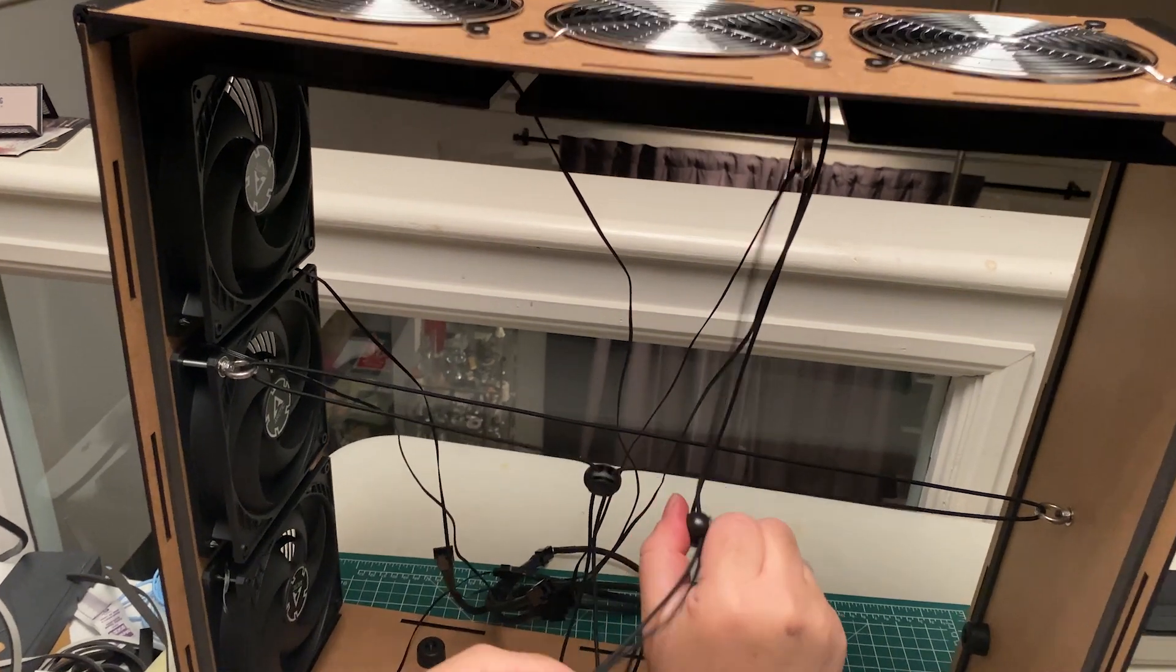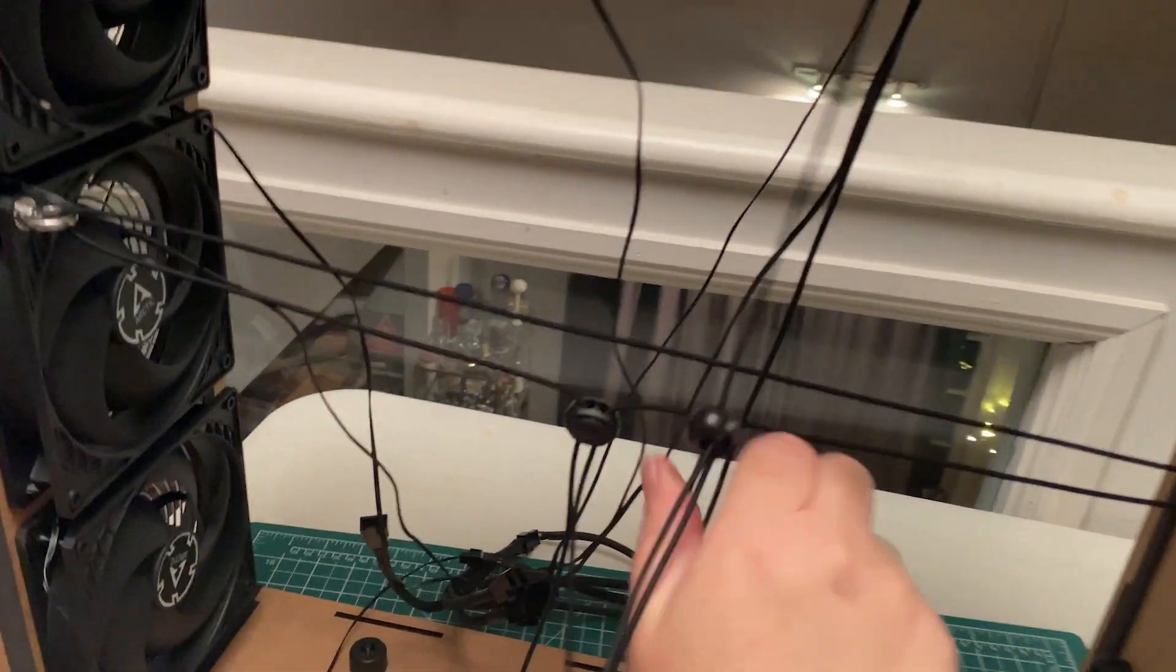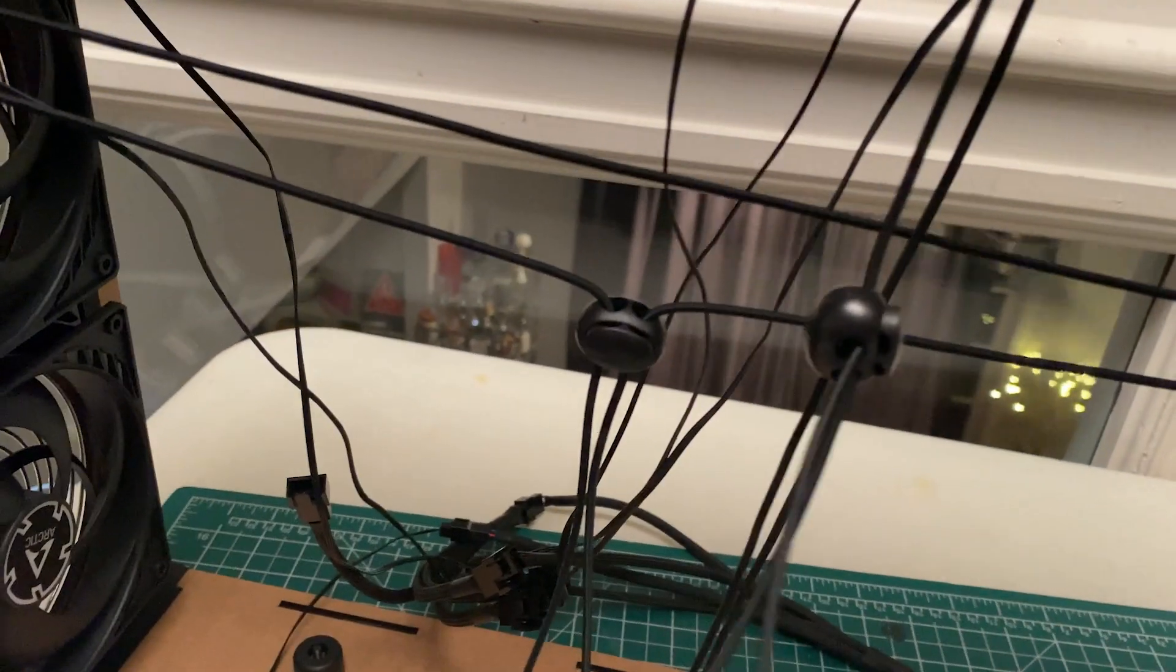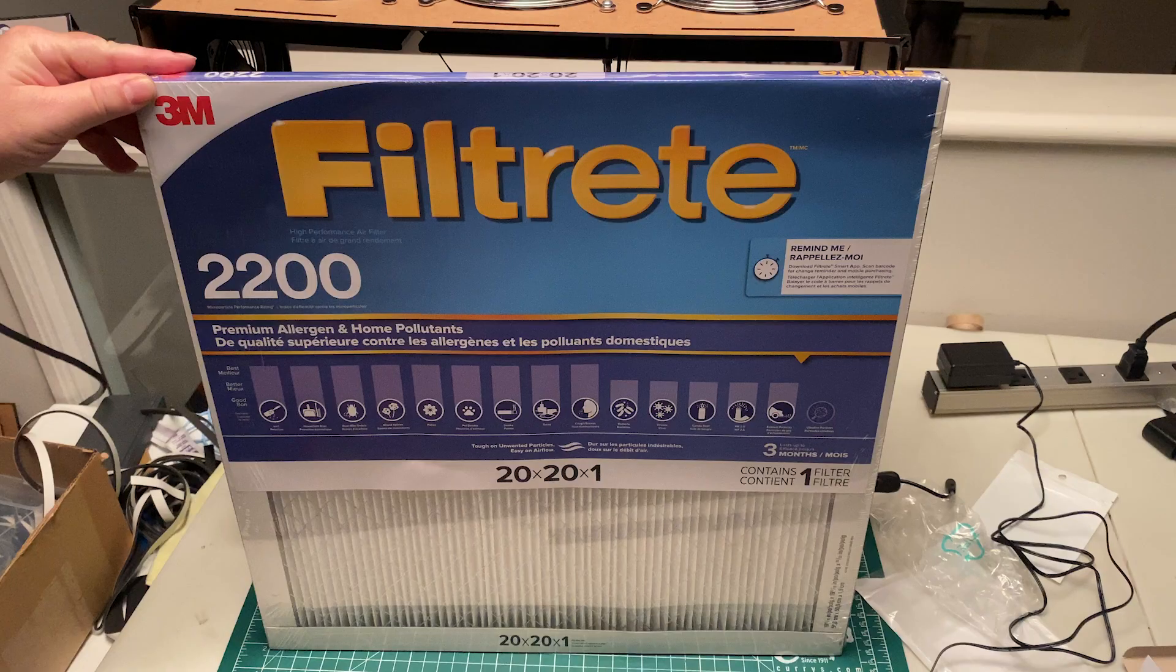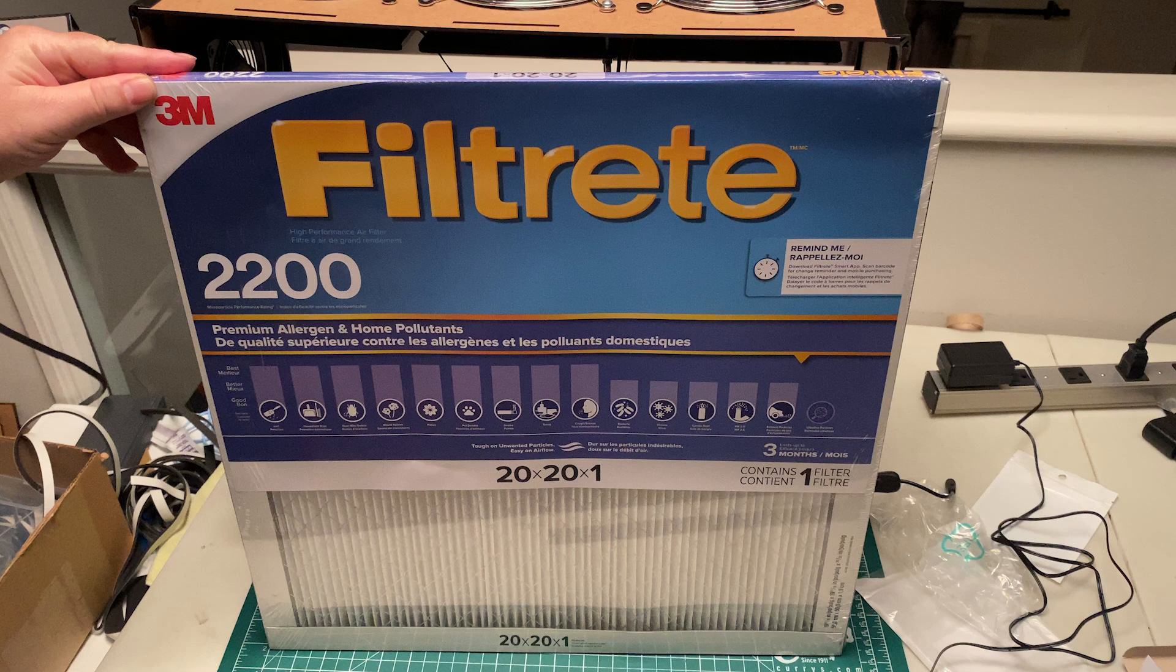Now it's time to install the filters. Our pre-built systems use the 3M Filtrete 20x20x1 size filter, either MPR 1900 or 2200. Both of those filters are MERV 13 rated. Any MERV 13 rated filter will work. You can even put 2 inch filters in.